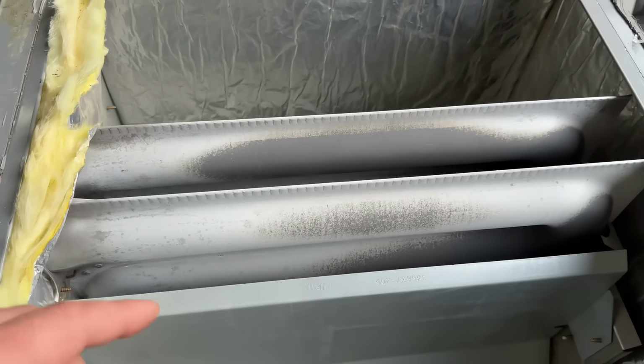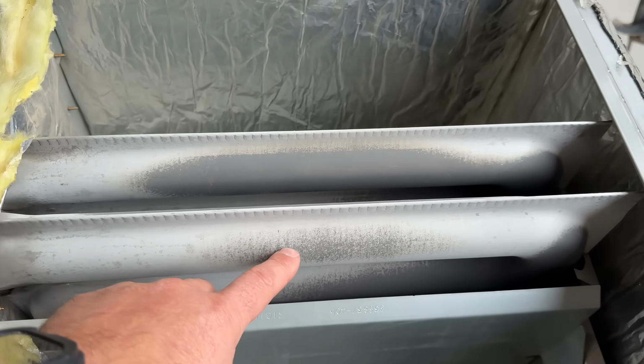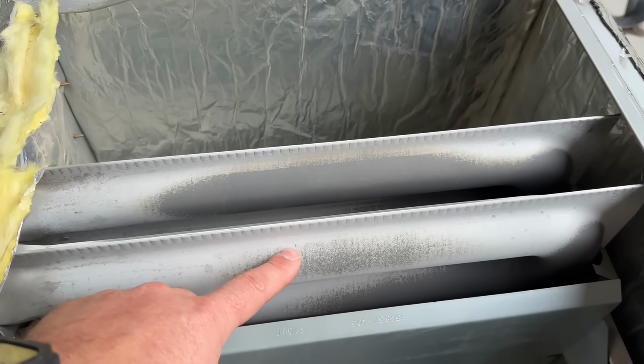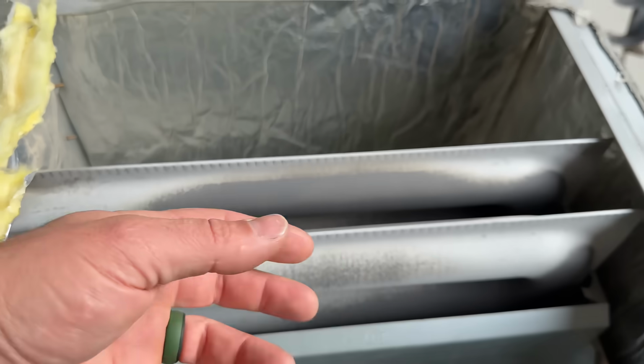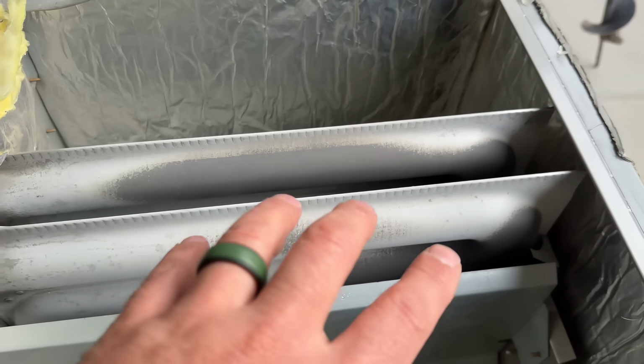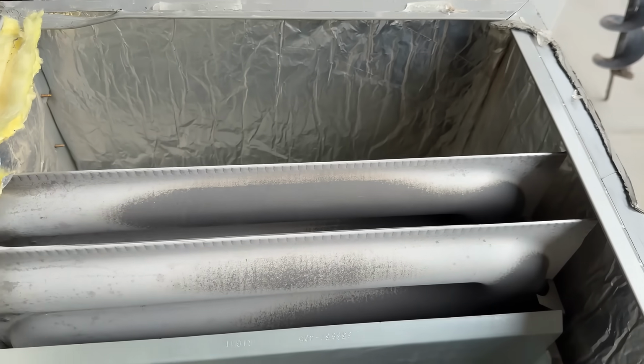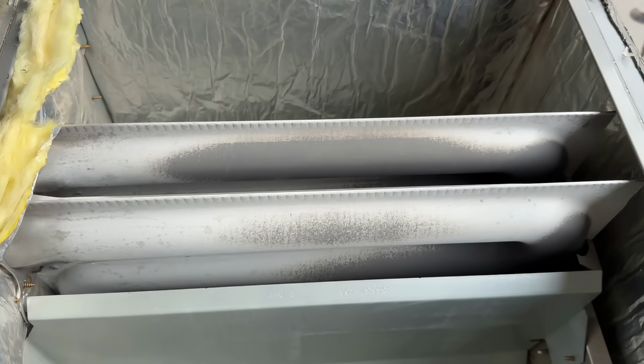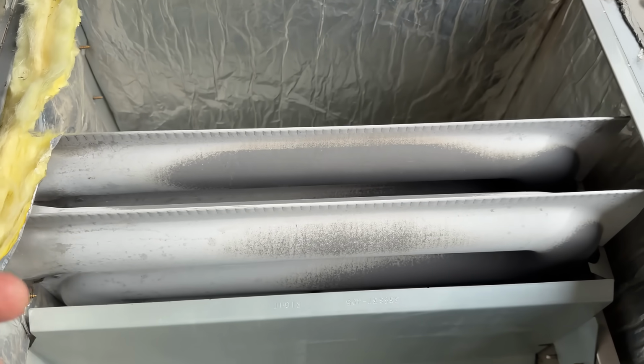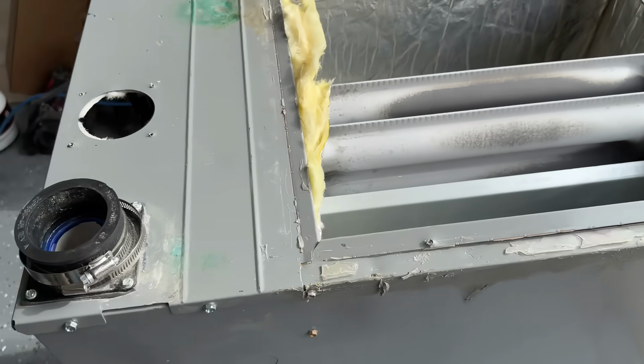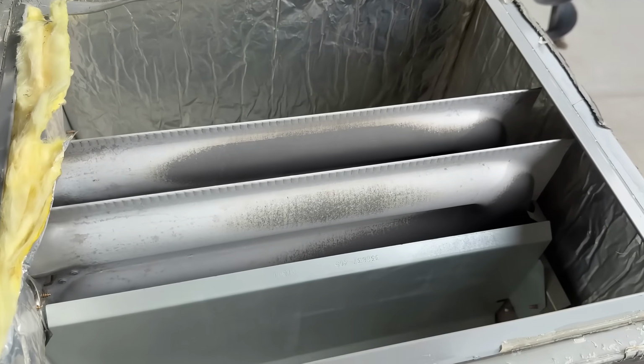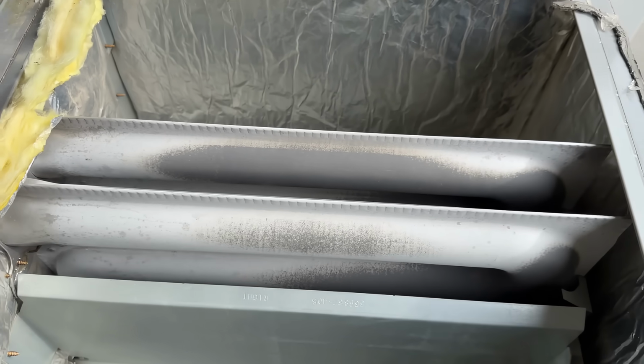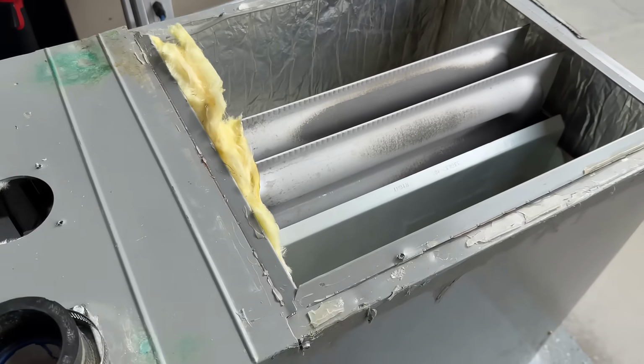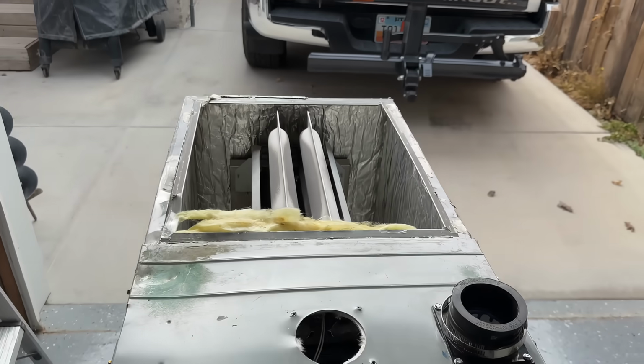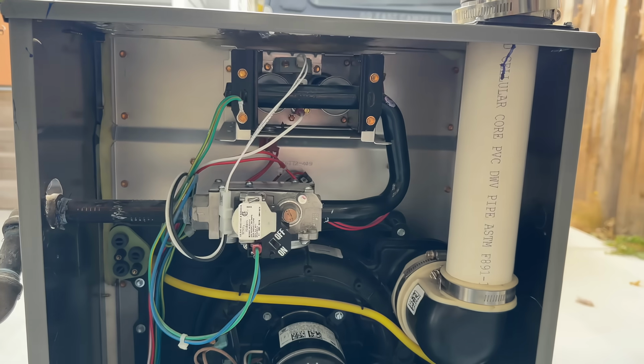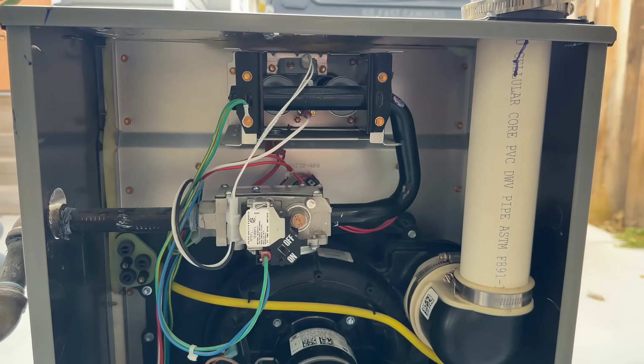So this is what a lot of people don't realize: if you have a crack here in the heat exchanger, the carbon monoxide, a lot of times, if not the majority of the time, is not escaping the heat exchanger. It's actually being sucked through the heat exchanger. So it's going to be pulling this air into the heat exchanger and then sending it outside. A lot of HVAC contractors will make this sound like it's a life or death thing, and it requires immediate action. Like, you have to replace this. We're going to turn the gas furnace off, and you can't turn it back on unless an HVAC guy comes and does it. And they really scare people into replacing their furnaces for an exorbitant amount of money. And it's really sad, but the whole purpose of this video is just to inform you of what to look for if your heat exchanger is really cracked and how to identify if it's not cracked.